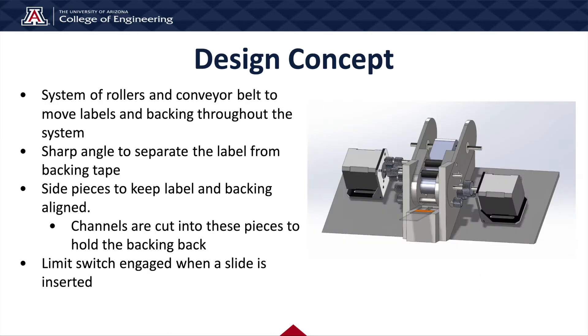Our design concept is that a lab worker could input a ribbon of labels into the system, insert a slide, and the system will label the slide. The label ribbon is accepted by our system and, using custom cut channels on each side, a conveyor belt in the middle, and rollers above, escorts the label ribbon around an edge. At that point, the label is released from the backing paper and placed on a slide, while the remaining backing paper continues running through the channels and is deposited to the rear of the system. The labels are detected by a laser, which triggers the stepper motors driving the conveyor to pause while waiting for an input slide. When a slide is input, it pushes a limit switch, which triggers the conveyor to move forward one step and label one slide.